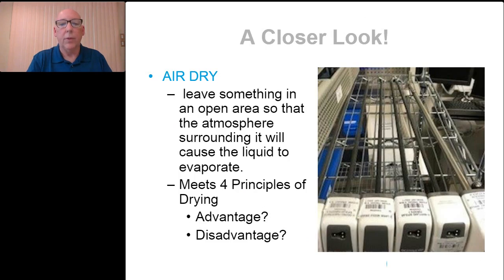So let's take a closer look at some of these techniques. As far as air drying devices, the exteriors of these devices, as you can see on the screen, will certainly air dry over a given period of time. There's no question about that. But you've probably noticed water dripping from them after they've gone through a sonic washer or automated washer. So how will simply air drying them evaporate moisture remaining inside? You're going to have to rely on conductive drying, which is basically temperature coming through the lumens, but that's going to take a very, very long time. And you don't know how long that time is going to take. Again, air drying doesn't cost anything, but is that good enough for the lumen devices? Is that good enough for the internal parts of scopes, robotic devices, etc.?